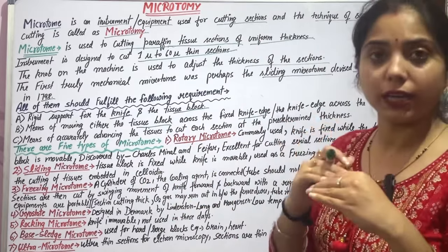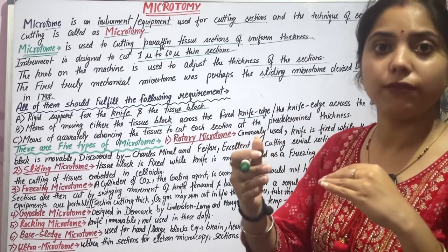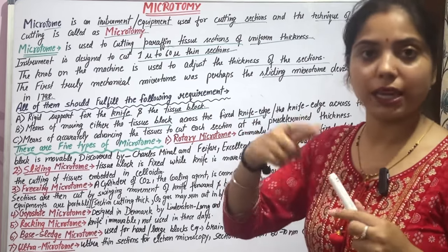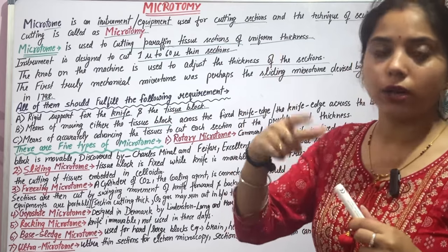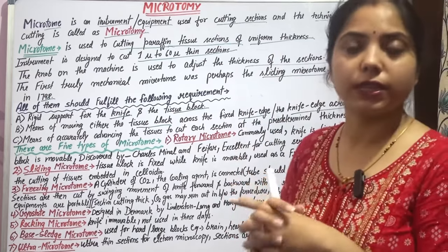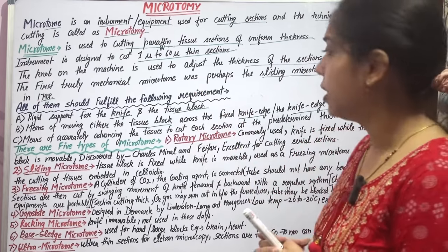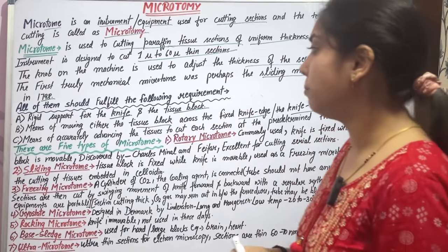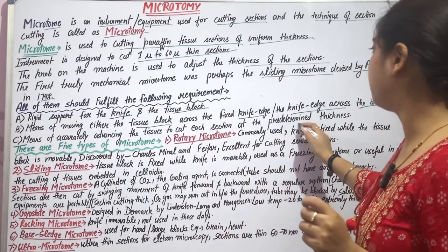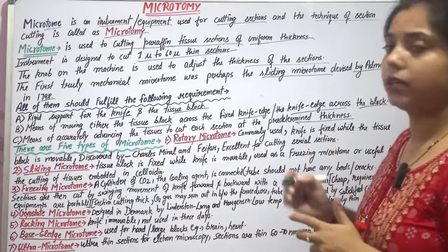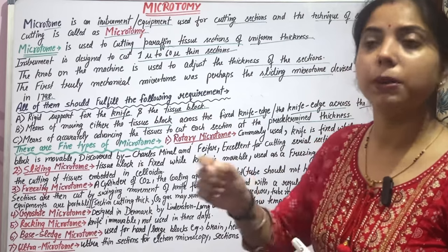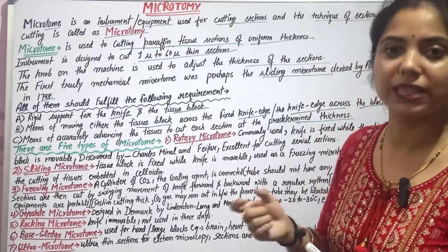If the tissue block rotates, the knife will be fixed. The block rotates and goes up to the top, then the knife cuts through. Additionally, there must be means of advancing the tissue to cut each section at a predetermined thickness, which can be adjusted beforehand.